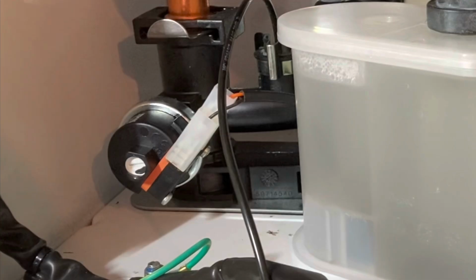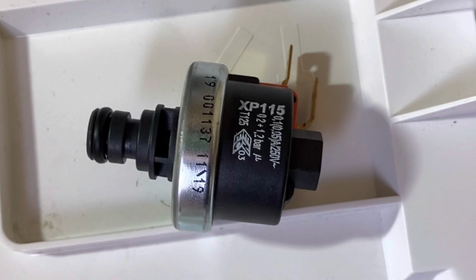This switch works slightly differently. It's a very simple concept. The contacts are open and closed depending on the pressure within the heating system. So for instance, when the pressure increases, the contacts close to create the circuit, and when the pressure decreases, the contacts open and the circuit is broken. However, on some older boilers, I think this actually works in reverse. So if you're working on an older boiler, make sure that the opening and closing can work in the opposite fashion.